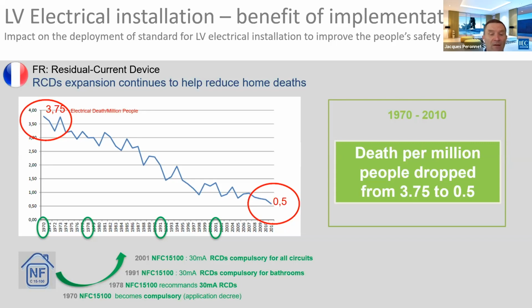Also, regarding the benefits of implementation, just to give you an example, in France, when we first introduced the equivalent of the IEC 60364, which is the NFC 15-100, which is really equivalent to 60364, in 1970 we had more or less 3.75 electrical deaths per million people. And implementing the different recommendations and requirements of 60364, and especially by pushing the 30 milliamp RCD for all the circuits, we reach nowadays 0.5 electrical deaths per million, taking into account that we still have a backlog of installations which don't implement the latest version of 60364.